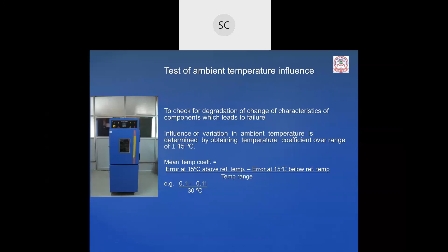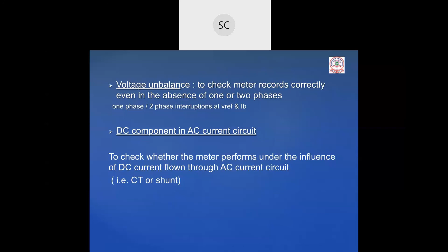Voltage unbalance: in case of voltage unbalance, one phase has failed altogether, maybe a fuse has blown out or the MCB has tripped, whatever the case may be. In all cases, the meter should continue to record correctly. And DC component: to conduct this test, we need another symmetrical meter, so that the positive half cycle is passed through the meter under test and the negative half cycle is passed through another dummy meter. Otherwise, my circuit will not close. For proper compensation, I need a balance of positive and negative pulses, so I use one more meter for balancing the input and output currents. Then accuracy will be maintained within the tolerance limits.